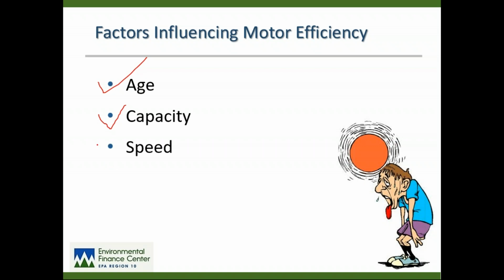The third factor is speed. Generally, you can buy most motors in the United States in several RPM ranges. 3,450 is real common. The next step down would be 1,740. The next step down from that would be roughly 850 to 900. And the next step down from that would be 600. For a motor that is loaded with the same work in terms of horsepower, the higher speed motor tends to be slightly more efficient. And that one surprised me. I would have thought otherwise.